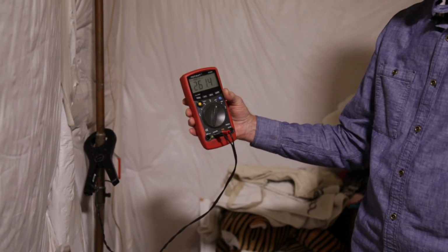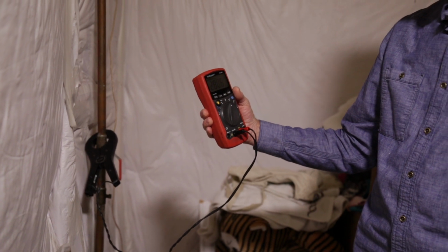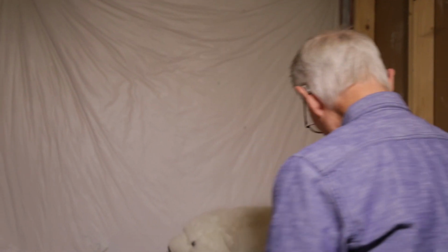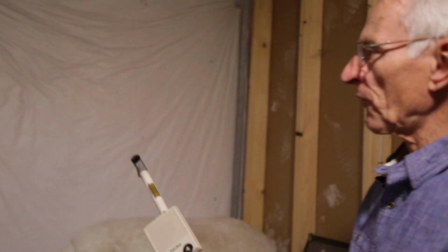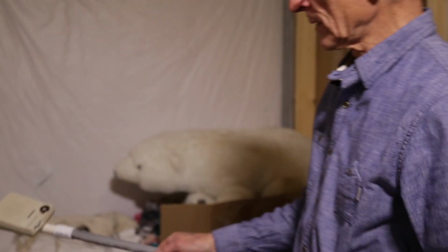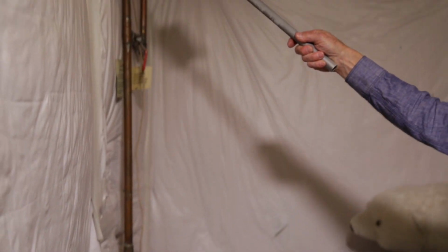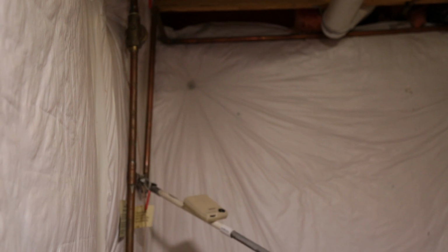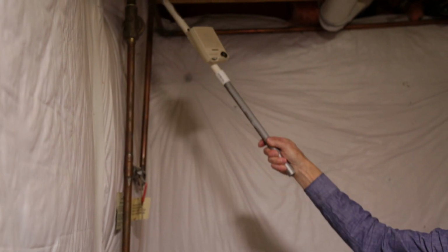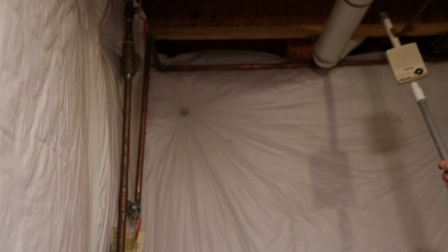We've actually took a look at this earlier, and it was up to 500 milliamps, or a half an amp flowing on the water pipe. I'll also point out to you that the current flow follows particular paths because it wants to get back to the utility, and it has to find a path in the house that serves that purpose. So if we turn this back on again and we look, we see that the current's going this way, nothing's going this way. The current goes this way, it goes across the ceiling.